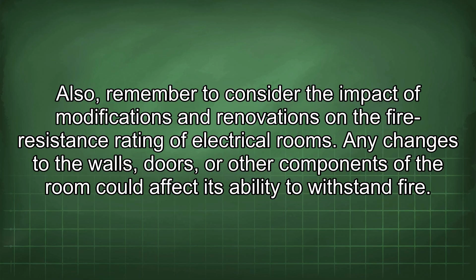Also, remember to consider the impact of modifications and renovations on the fire resistance rating of electrical rooms. Any changes to the walls, doors, or other components of the room could affect its ability to withstand fire. It is important to ensure that any modifications are performed in accordance with applicable codes and standards and that the fire resistance rating is maintained. This may involve using fire-rated materials, sealing penetrations, and verifying that doors close and latch properly.